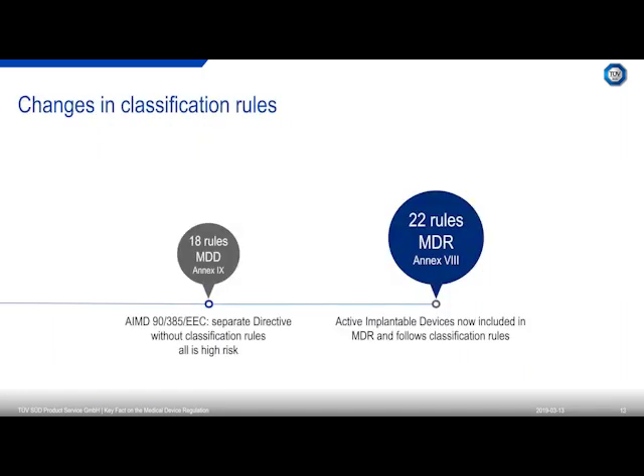The classification of medical devices is still something that has not changed too much, except for some rules that have changed and now come up with a higher classification of the device. Under the MDD, we had 18 rules to follow. And under the AIMDD, we had no rule to follow because all AIMDDs were high-risk products. Therefore, there was no classification in the AIMDD. Now we have 22 rules under the MDR, and they are all covered in Annex VIII.